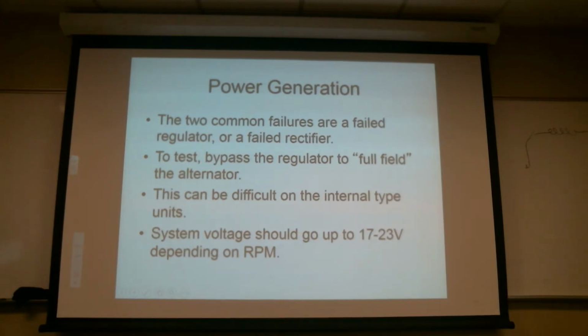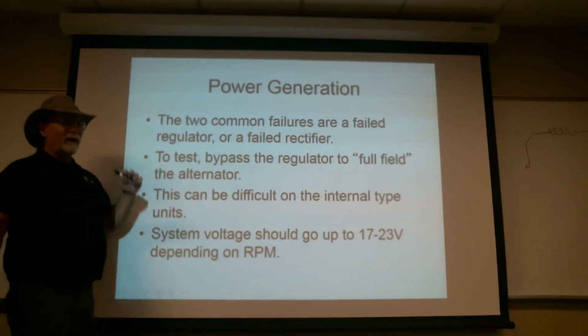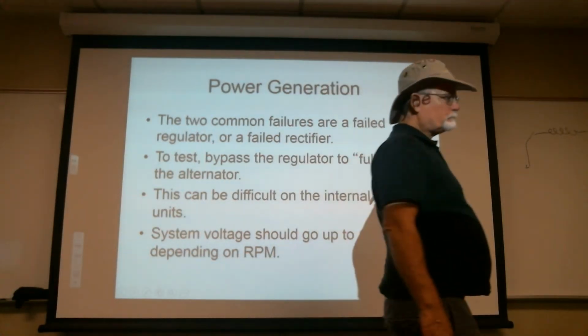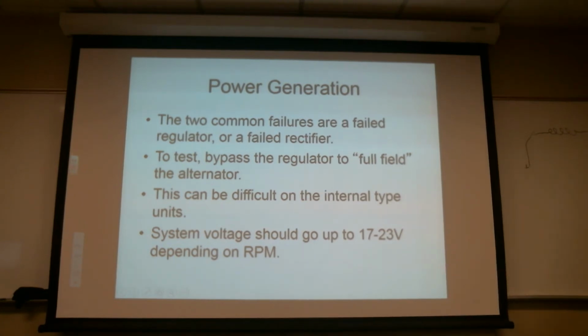Well, commonly what fails on these, occasionally it is the brushes. They're in there long enough for the brushes to wear out. More often though, either the rectifier plate, just from heat and vibration, breaks itself and diodes start breaking, or the regulator fails in one form or another.